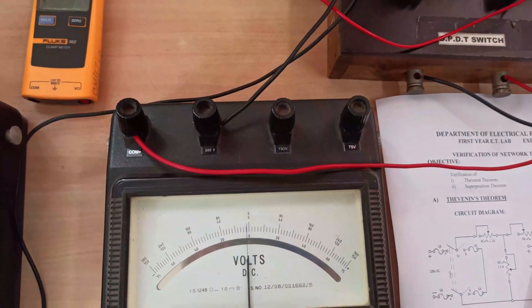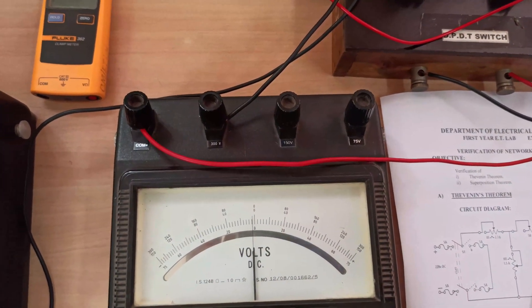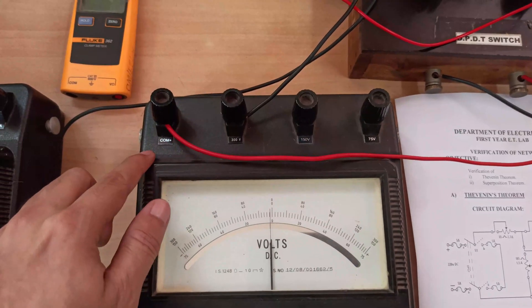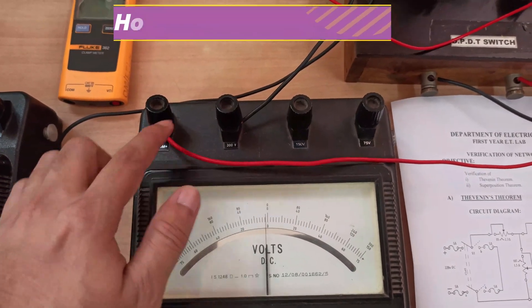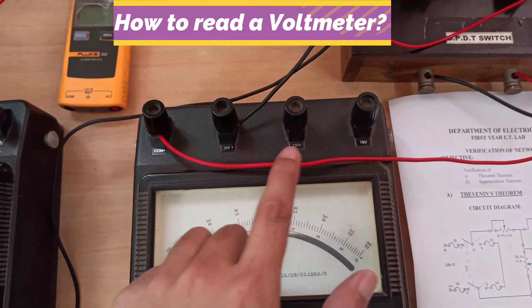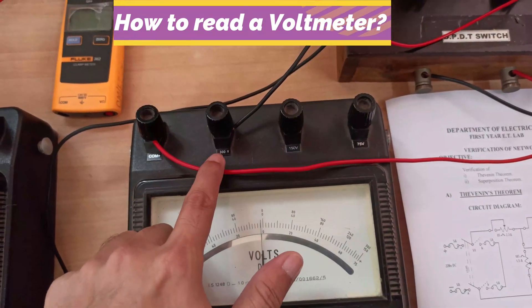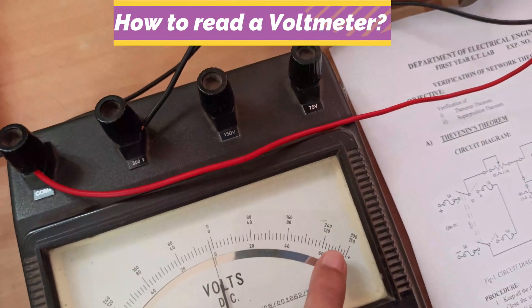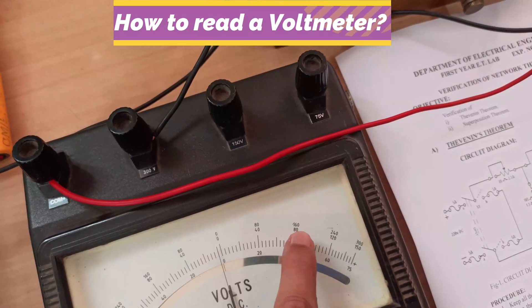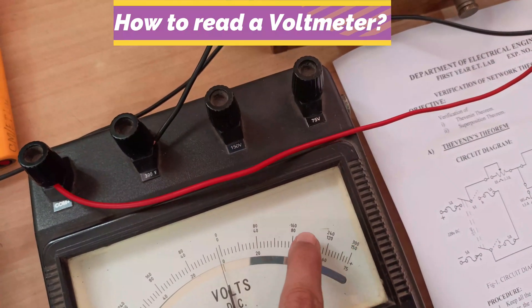In the voltmeter you have three different ranges. You will be connecting one wire to this common terminal and the other wire to any of these three ranges. If you connect it at the 300 voltage range, you should be looking at the display at the top readings, that is the 300 voltage scale.